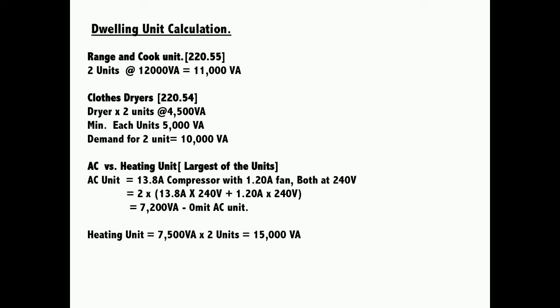The next load to take into account is the range and cook unit. In this question we have a range of 12,000 VA, but that's just for one floor, so we need two units to account for. Two units at 12,000 VA, according to Article 220.55, would leave us with 11,000 VA demand for the entire range load.